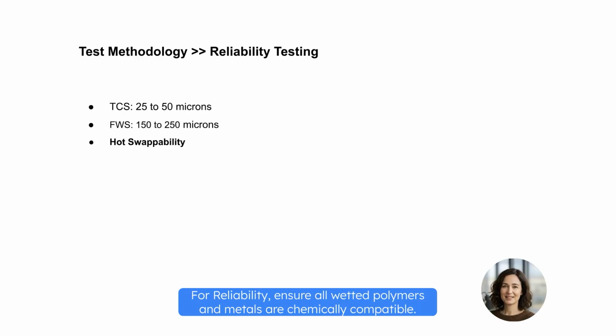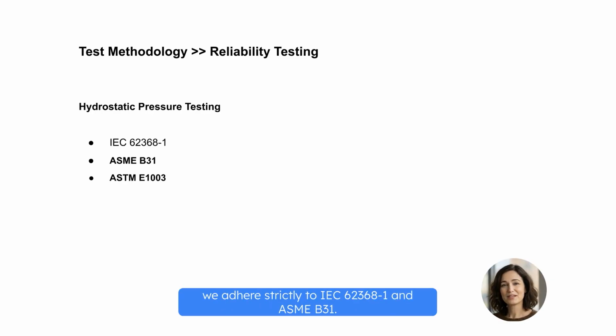For reliability, ensure all wetted polymers and metals are chemically compatible. Then, respect the filtration hierarchy. We demand fine filtration for the TCS loop, 25 to 50 microns, versus a coarser 150 to 250 on the facility side. Crucially, for operations, the best practice is hot swappability. You must design pumps and filters to be replaced on the fly, ensuring ease of maintenance without shutting down the cooling. For hydrostatic pressure testing, we adhere strictly to IEC 62368-1 and ASME B31.